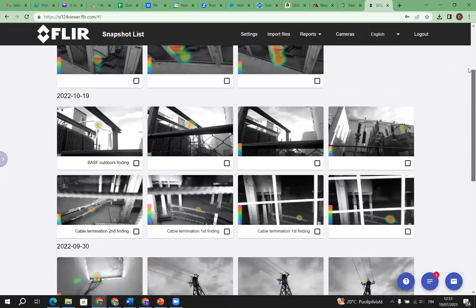When we're talking about transformers, remember I was mentioning them? This is an example of, I think, a dry type transformer, a current transformer here, I didn't introduce the volts, I think it was 35. Anyway, this is giving a very high severity because it's a transformer, so the camera can find partial discharge in the transformer. In this case, it's in the base of the transformer.